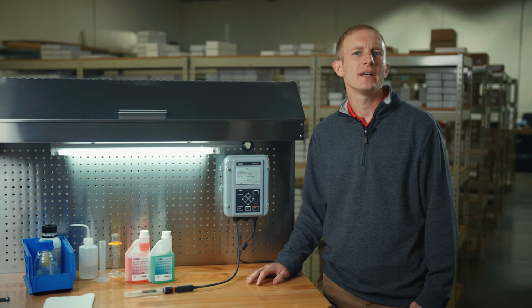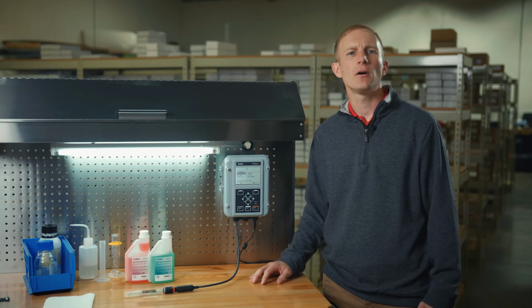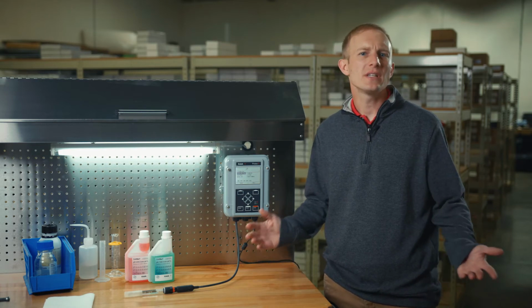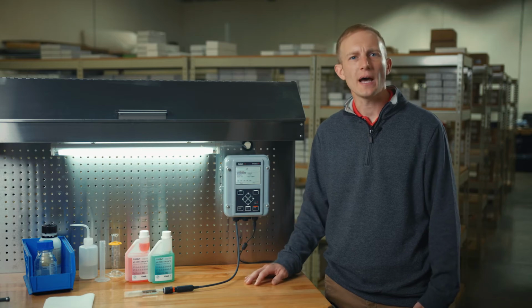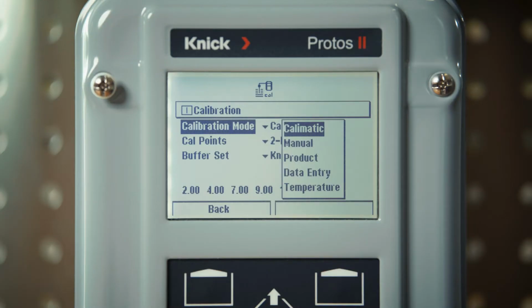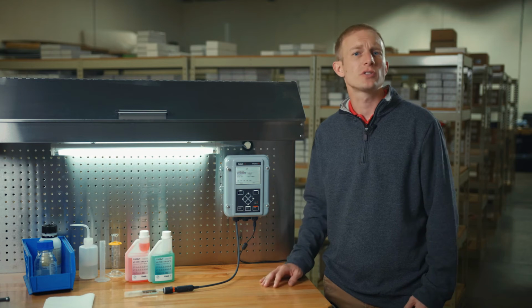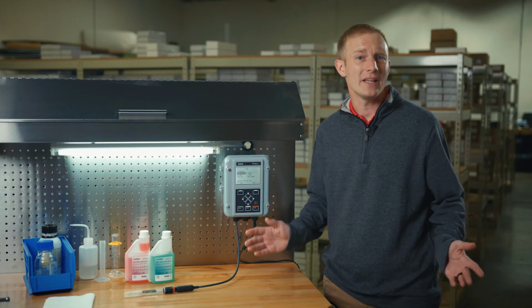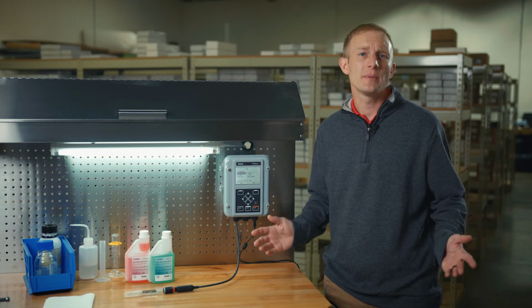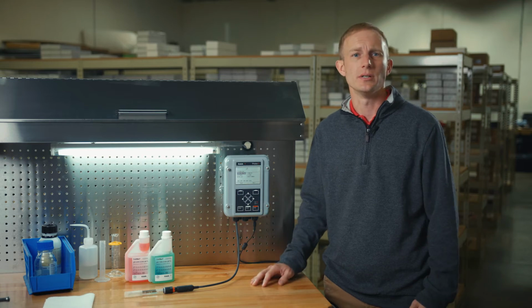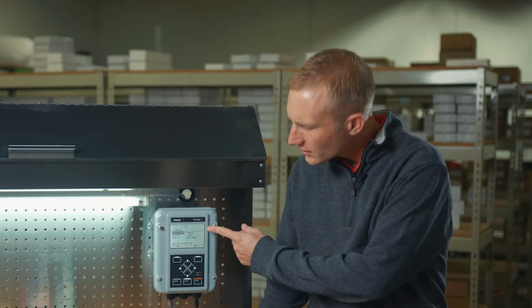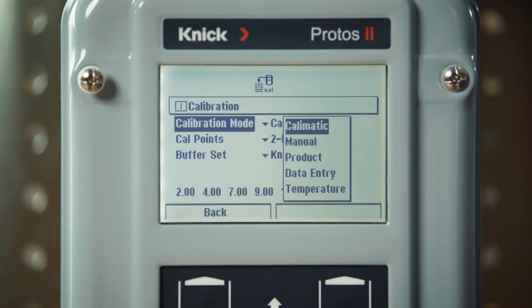I will be conducting a Calimatic or automatic calibration today, but here you can see the different options available for calibrating. The Protos enables us to perform a manual calibration, a product calibration or a single point standardization, adjustment of the electrode slope and 0 point via data entry, and lastly, adjustment of the internal temperature detector. Ensure that Calimatic is selected here before proceeding further.